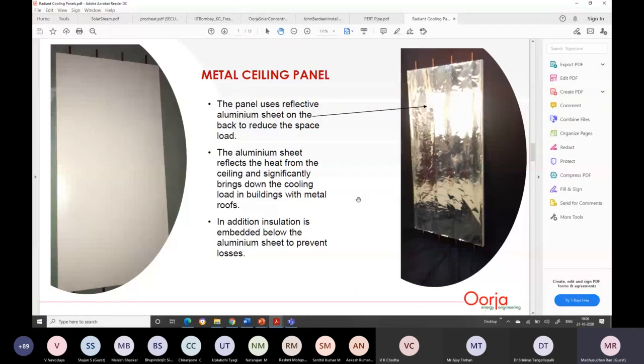So what we did was use an aluminum reflective sheet with 80% reflectivity in our panel, so that if that is a major source of heat, why not reflect that heat and exhaust that air? Once we did that, the load fell by 40%. We didn't have to bring that heat in and then use air conditioning to remove it. The best way was to just take it away and not let it enter the space.